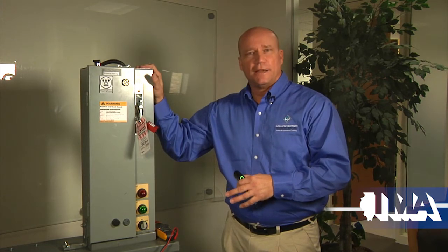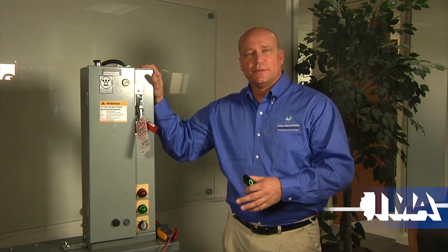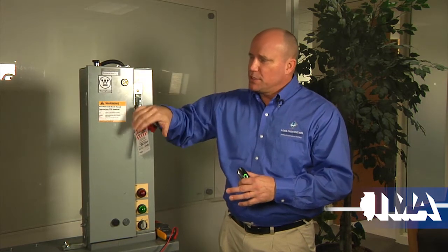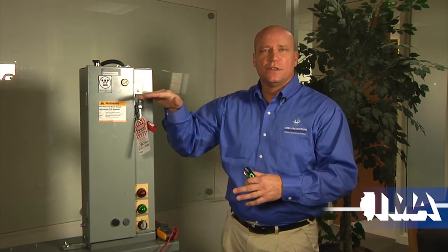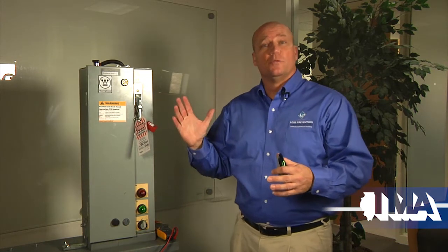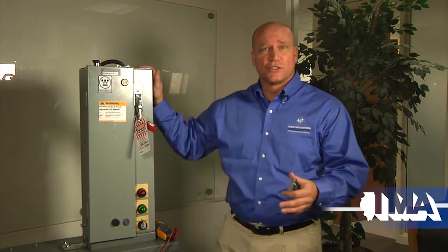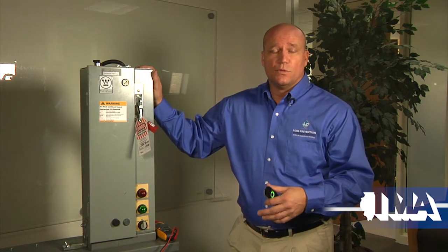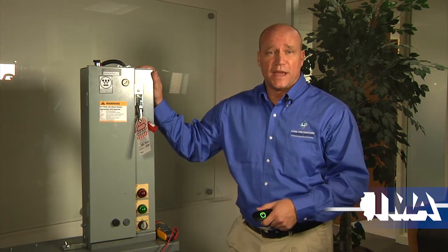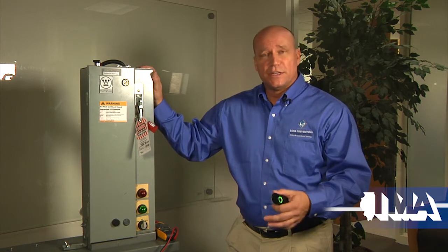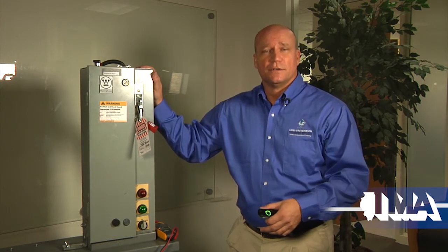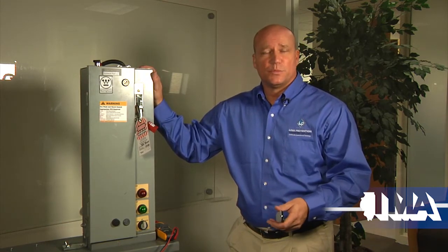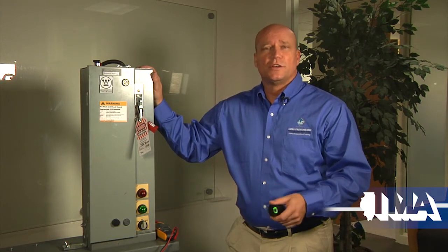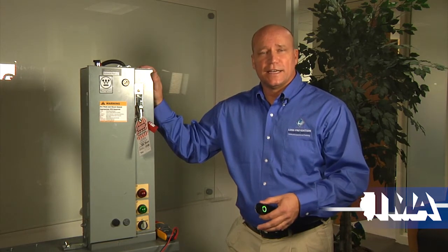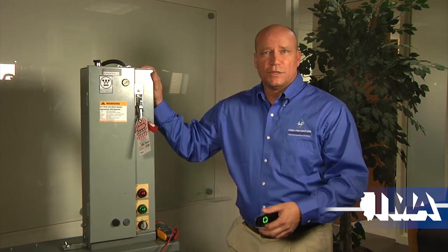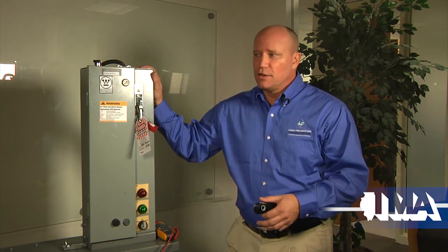So how could you find power when you don't expect it? Sometimes switches fail. If you operate a switch and the switch is internal here, and one of the three phases happens not to open, maybe somebody closed it into a direct short previously, and one of the three phases still has voltage passing through it. Another possibility is there are modifications that you may not be aware of, that may not be on electrical diagrams or prints, and those are probably what you're going to be utilizing to develop your lockout tagout isolation, and you may have unfortunately missed something. And then also mistakes happen.